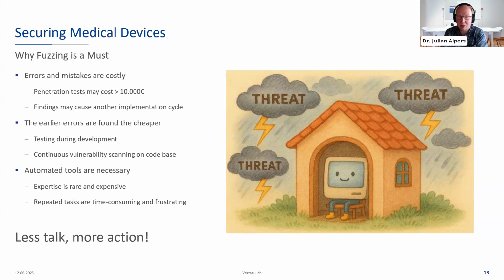So let me give you an example. You have a Bluetooth connection, and one of your requirements is, hey, this Bluetooth connection has to be encrypted because we do not want anyone to sniff information in plain text. So your software developer sees this requirement, defines what they want to do, implements an encryption, and functionally it is working. There is no plain text readable anymore, the Bluetooth connection is encrypted. But now your penetration tester comes and tells you, okay, yes, you have an encrypted Bluetooth connection, but you used a 7-year-old algorithm, which is highly outdated, and any open source library or tool I can find on the internet is able to crack your connection. So you have passed the cybersecurity requirements test because functionally it's working, but it does not reduce your threat at all, because anybody with a little bit of technical expertise can use these open source tools to crack your encryption.